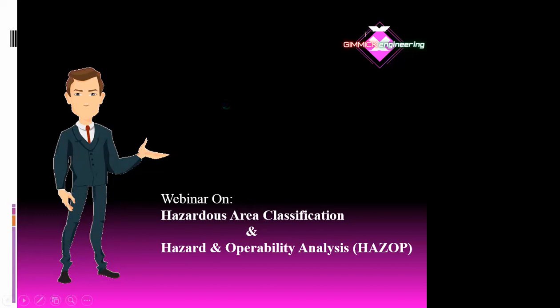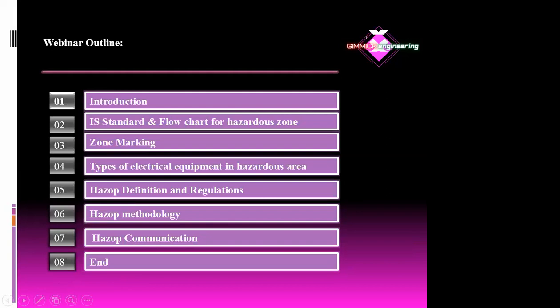In this case, which one is suitable? You should take the chemicals we are using for the process. For example, take the chemical having the lowest auto ignition temperature. Mostly, industries follow hexane. Hexane has an auto ignition temperature of 210. In this case, we have to take 80% of the auto ignition value, so you have to take 160. With respect to 160 degrees, the nearest classified motor is the T4 motor. So a T4 motor is fair enough to handle this operation, because even though hexane requires 210 degrees as an auto ignition temperature to catch fire, the motor will never go beyond 135 degrees, so we are safer.